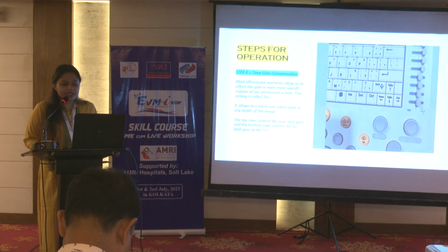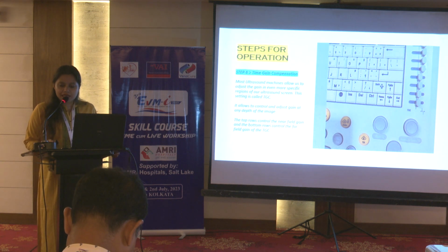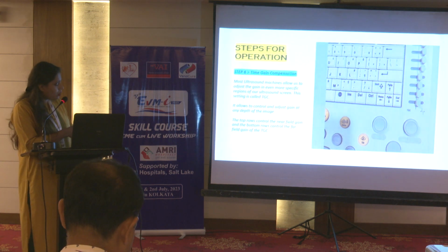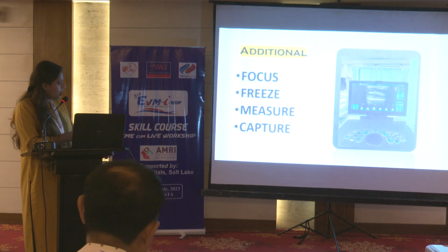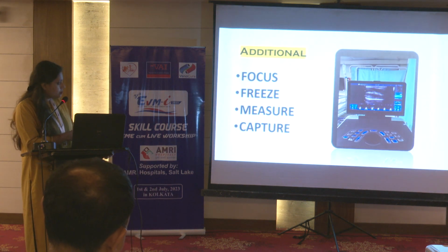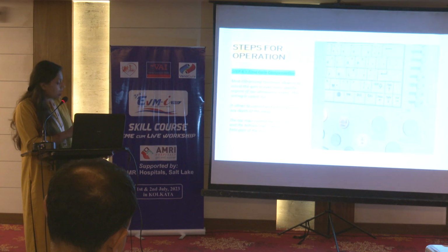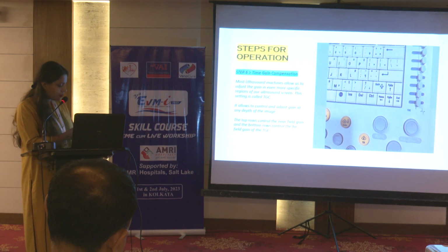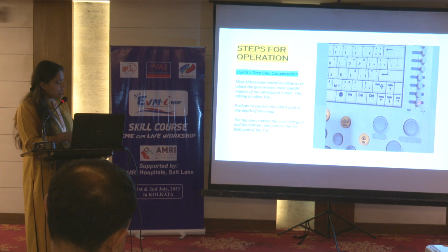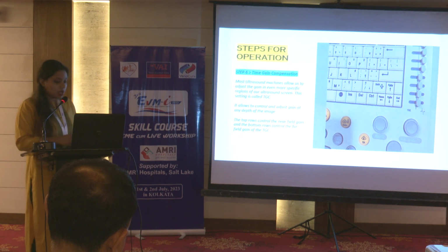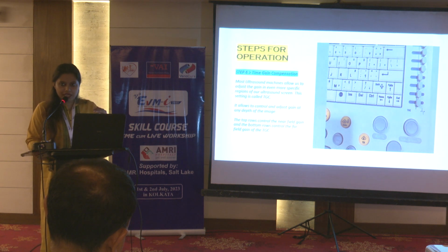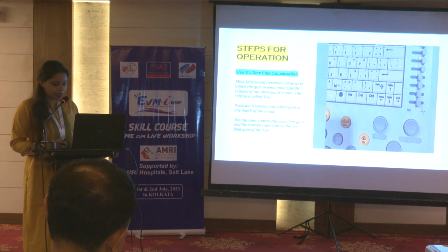Now the next step is the time gain compensation. The TGC switches that we have, we can see in most ultrasound machines. These are used to make gain adjustments at a specific location. That is, when we use them, we can adjust the structural gain at the near field view or at the far field view. We can increase or decrease accordingly.